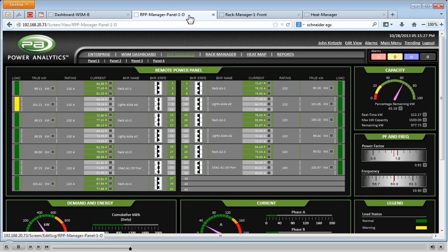The RPP Manager simplifies the configuration of any device with panel schedules and, provided that there is monitoring of branch circuit currents, permits the efficient use of the available power on RPPs by providing information about real-time power usage and capacity. It provides an extraordinarily intuitive visual representation of the real-world panel. All of the information you'd expect is present. The available slots, as you'd see in a real panel.